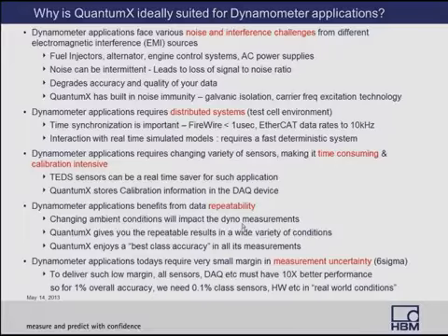For example, the QuantumX 840A module will work up to 65 degrees Celsius ambient conditions and still maintain accuracy. It enjoys a best-in-class accuracy for all the measurements we do, between 0.01% and 0.05%, depending on the module we choose.